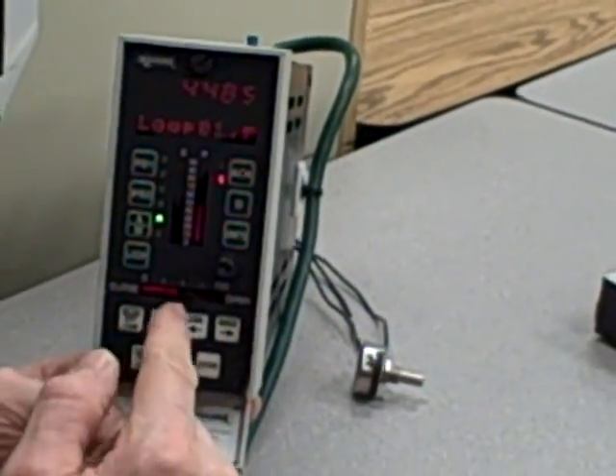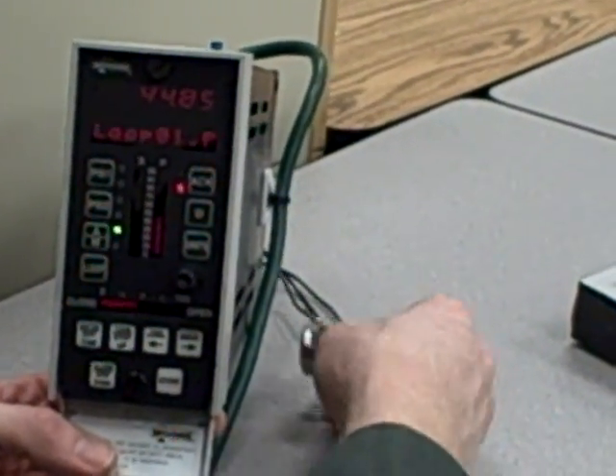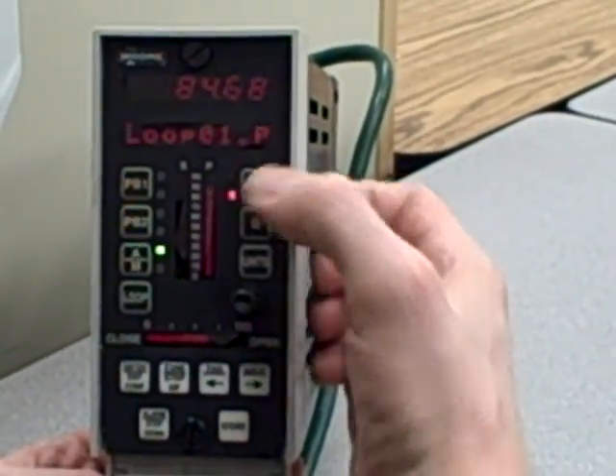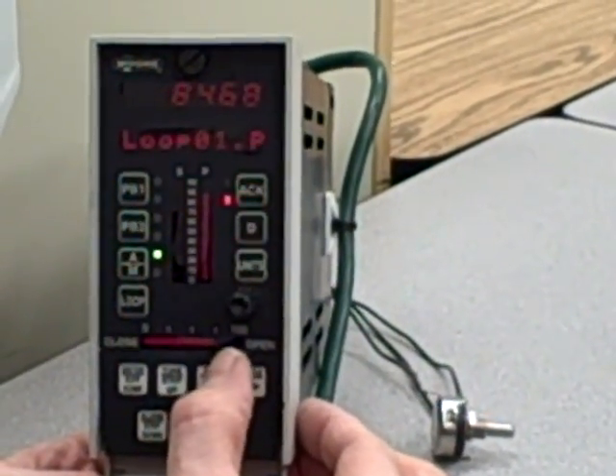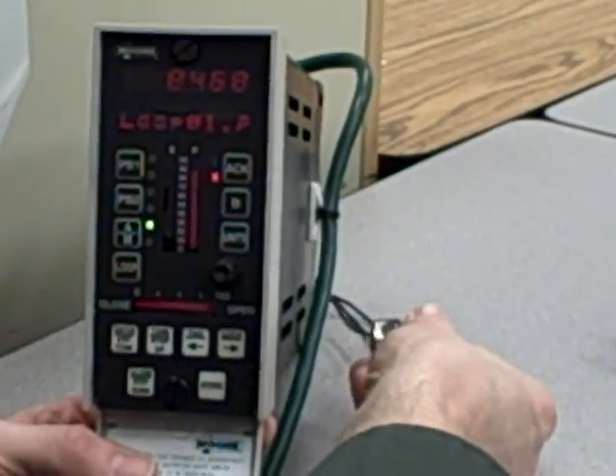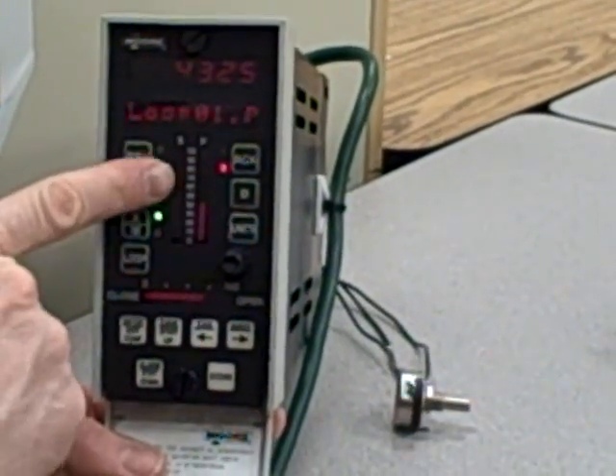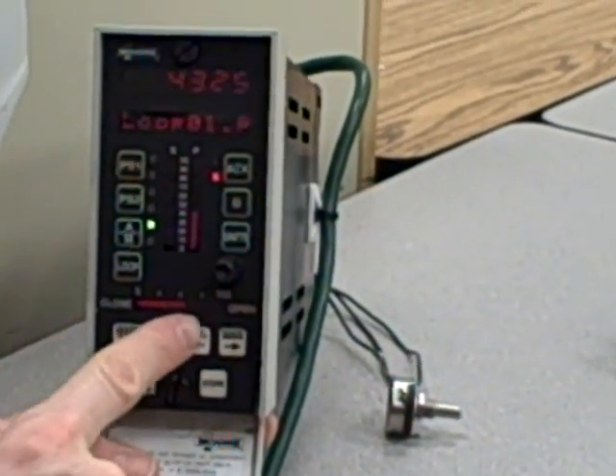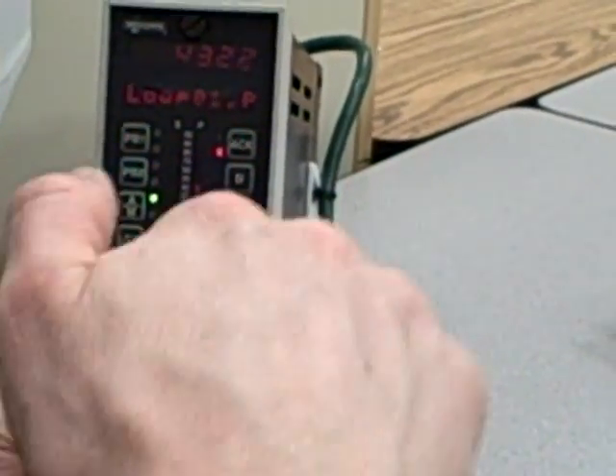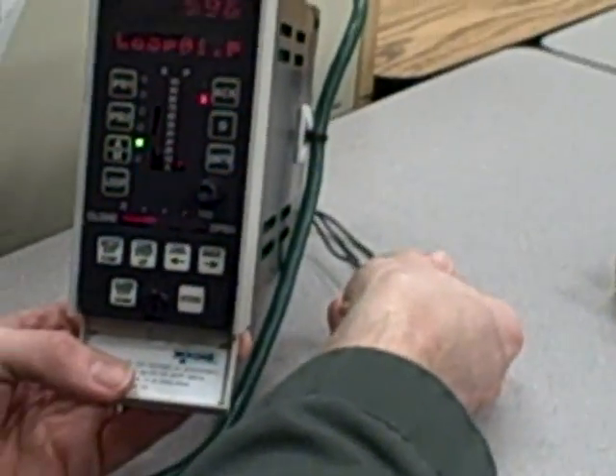Now when I move the potentiometer up and down, we should see a lag function. So watch as I move the potentiometer up, we see the process variable bar graph spike up and the valve settles into its new value. It's climbing like an RC time constant function. If I move it down, we see a sudden spike on the P bar graph and the valve bar graph slowly settles in, asymptotically settles into its lower value. That's a pure lag function right there.